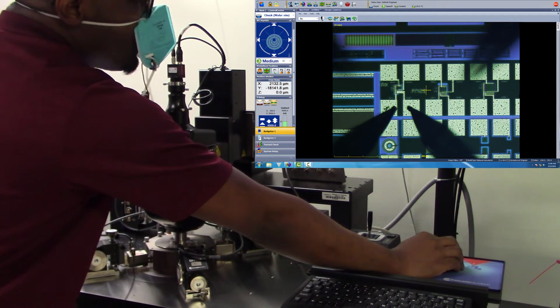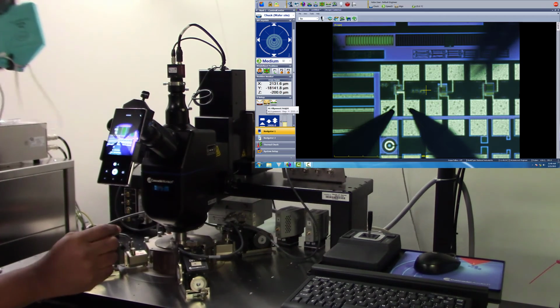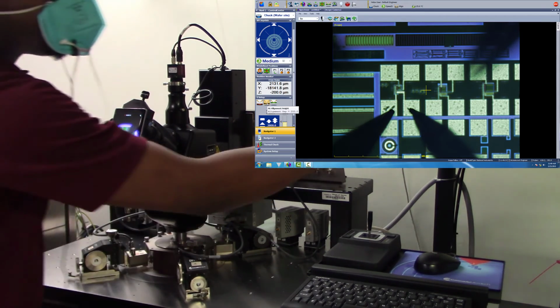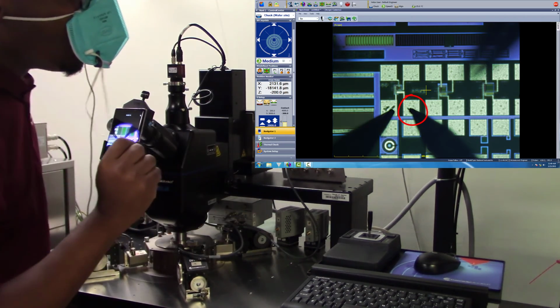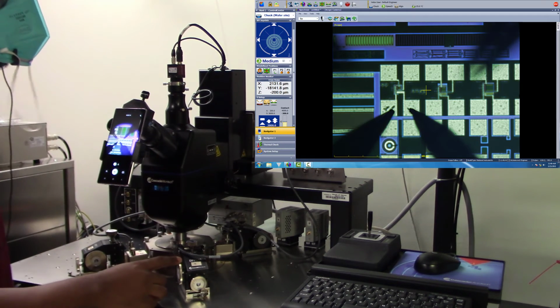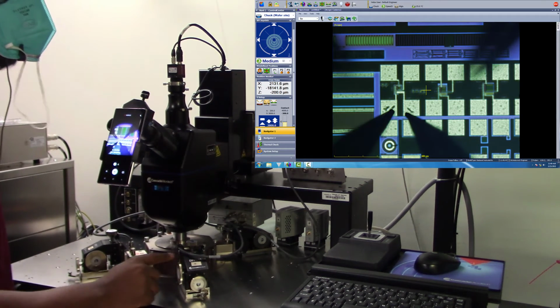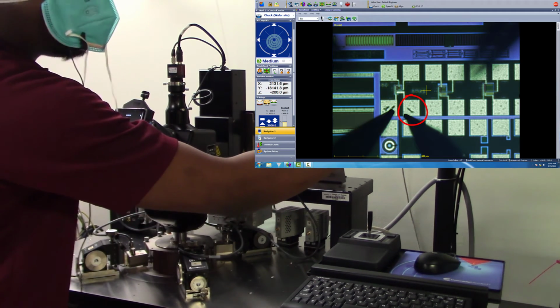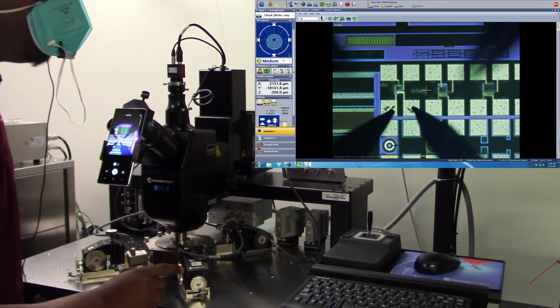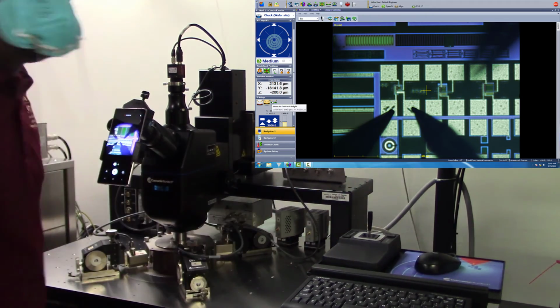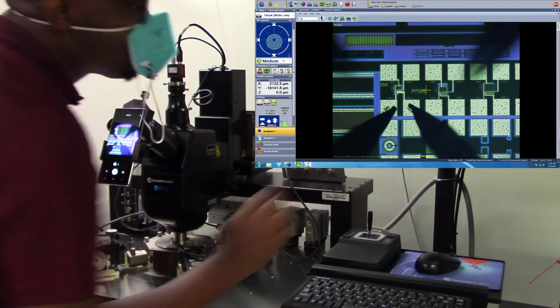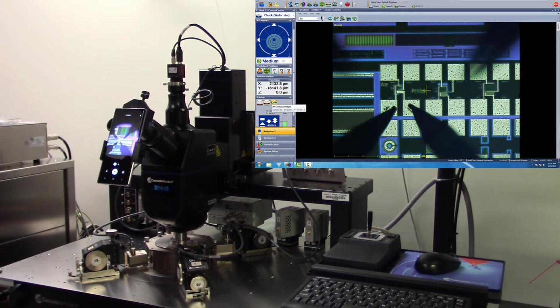To verify the contact again, you go back into alignment height and move your device. As you can see from alignment height, you can see a very small scratch on our device. If you are not sure about the scratch, you can adjust your X or your Y movement to verify if you have the scratch on your device. And as you can see there, we have a scratch on our device, and what it means is that once I place my probe tip back on my device and go back into contact mode, all of my probe tips should be in contact with our device. Once that is done, you go down into the semiconductor device analyzer and do your setup for what kind of measurements you need to take. So basically, that is how you land your probe tip on your device.